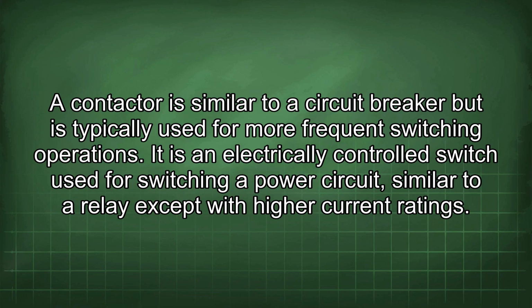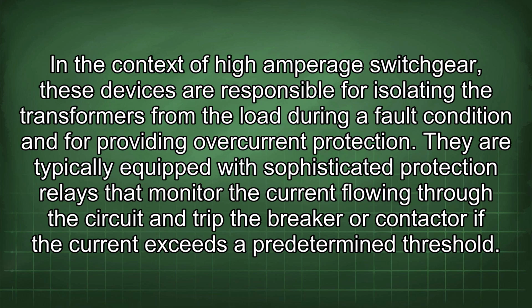It is an electrically controlled switch used for switching a power circuit, similar to a relay except with higher current ratings. In the context of high amperage switchgear, these devices are responsible for isolating the transformers from the load during a fault condition and for providing overcurrent protection. They are typically equipped with sophisticated protection relays that monitor the current flowing through the circuit and trip the breaker or contactor if the current exceeds a predetermined threshold.